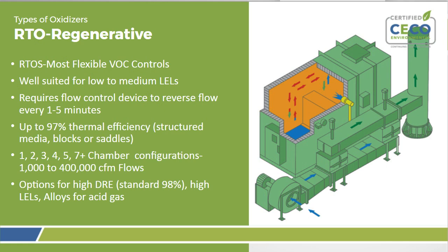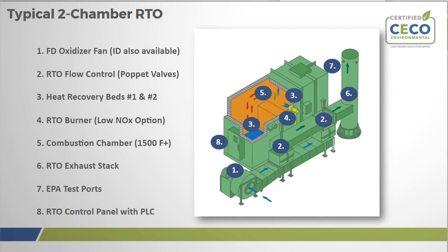So this is a typical 2-bed RTO, kind of the easiest to explain, and the rest are all variations of this. So on the right here, the 2-bed RTO recovers heat via 2 ceramic media beds. Process air is brought in below one of the media beds, which preheats the air before entering the combustion chamber. That's number 5 here. Then it goes down into the second bed, which then recovers heat from the air. So again, the process is preheated, goes through the combustion chamber at about 1,600 degrees for a fraction of a second, around a second. Then it exits through the second bed, which removes heat from the process.